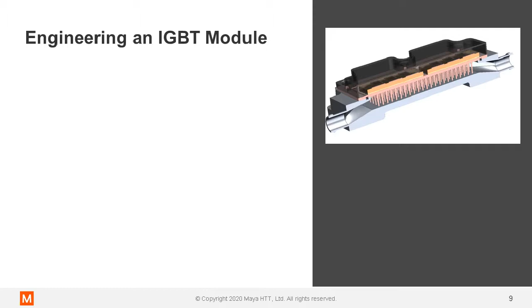Modifying the PCB board on an IGBT to meet thermal constraints is not feasible. Redesigning the cooling system would be the simpler option. In cooling systems, increasing the flow rate will increase the heat transfer coefficient between the fluid and solid, leading to lower chip temperatures.